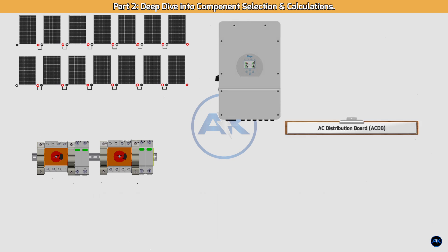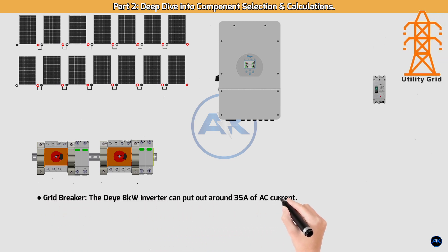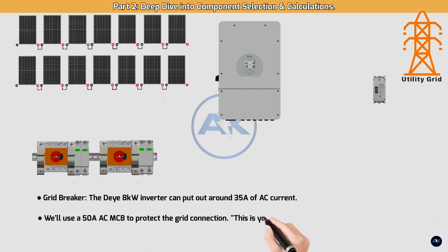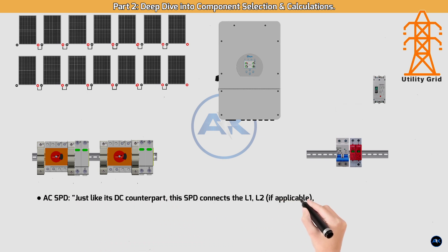AC distribution board (ACDB) and protection relays. Grid breaker: the Deye 8 kW inverter can output around 35A of AC current, so we'll use a 50A AC MCB to protect the grid connection — this is your inverter's gateway to the grid. AC SPD: just like its DC counterpart, this SPD connects the L1, L2 (if applicable), and neutral lines to the ground bus bar inside the ACDB. It's your last line of defense against grid-side surges.